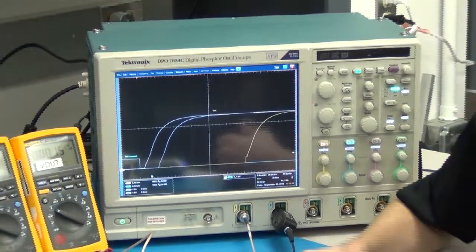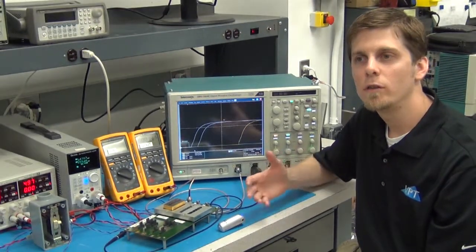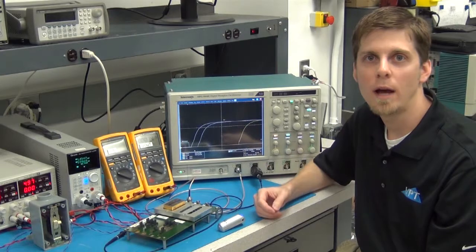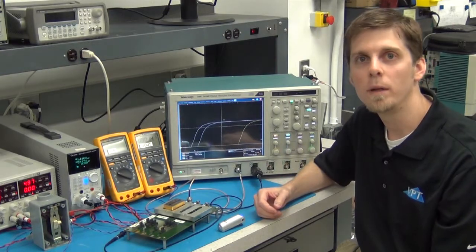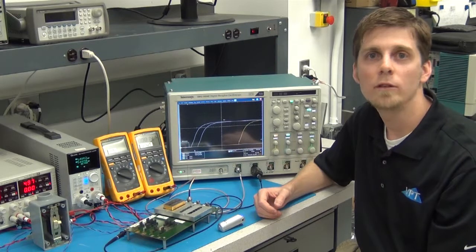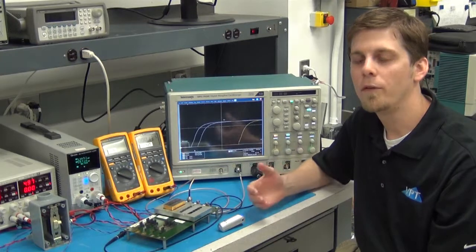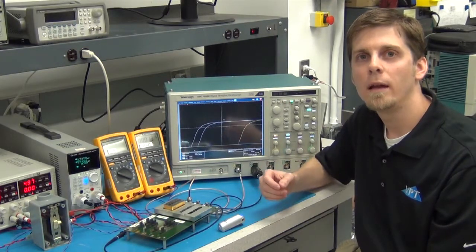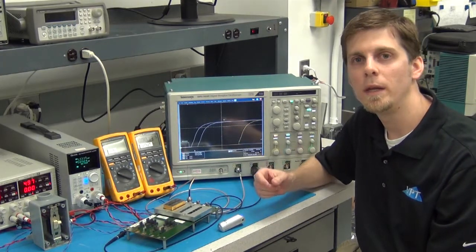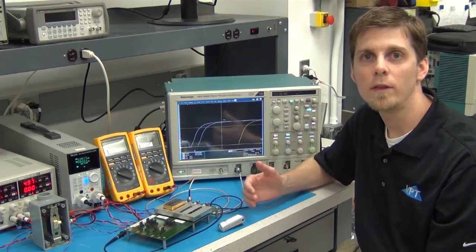So today we have talked about the inhibit function in our converters and general concepts about how to drive the inhibit pin. Make sure to use open collector or an open drain type circuit and do not drive it with an external voltage or TTL chip. And we've also shown how you can add a capacitance from the inhibit pin to input common in order to delay the turn on.